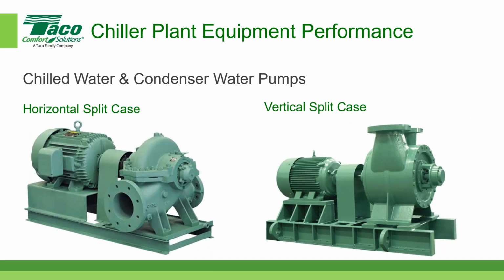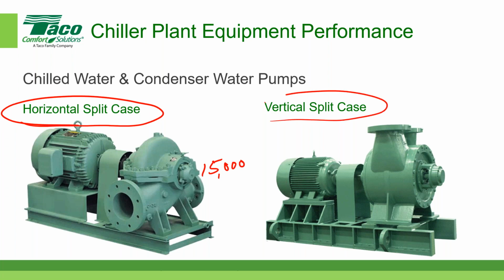And the other category are horizontal split case. This is usually for much larger systems. These pumps can go up to 15,000 gallons per minute. Roughly the same for vertical split case pumps. I think they're a little bit less. Do you remember, Brett, how much these go? I think they're up around 12, aren't they? The verticals, yeah. Around 12,000. We can look that up and we'll give you some more specific numbers. So those are the pumps.